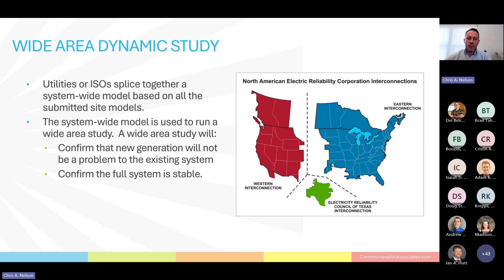And they will want to make sure the whole system is stable. If you have an unstable system, let's say 20% of your generators are not modeled well, it's really hard to get that flat run to begin with so you can actually see what's wrong. If it doesn't run, like if the voltage profile is bouncing back and forth without any disturbance, it's hard to really tell what the cause is when you put a fault on the system. So it's important to have the full system be stable, not just the one generator. We've worked with utilities where their model was not very good, and it takes a lot more work to try to clean up and make it work.